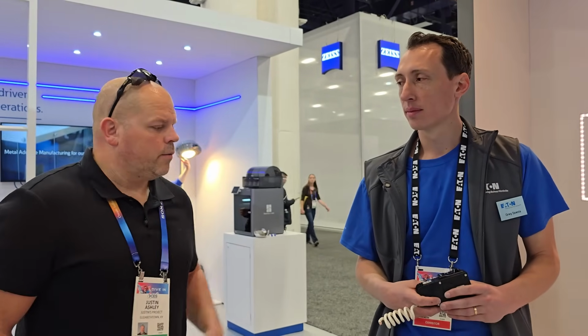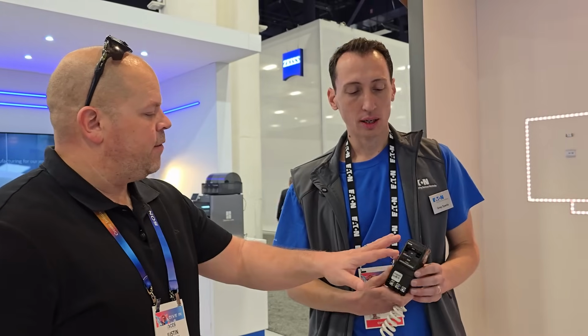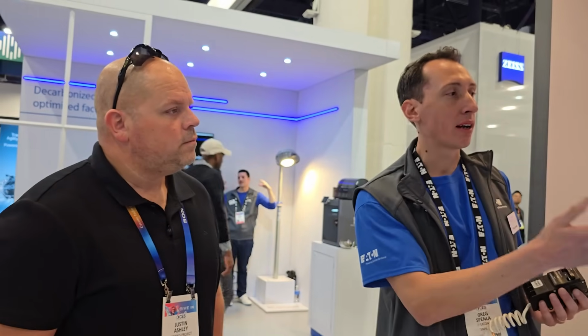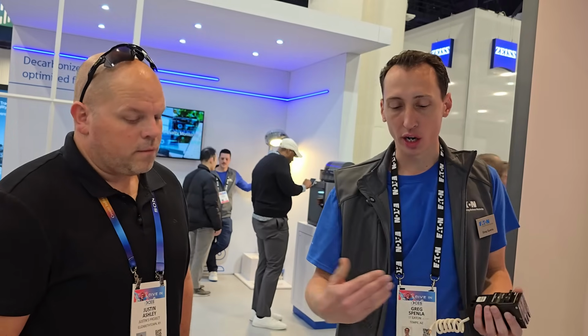All right. So you've got this in how many amps? What's the largest? This will be 15 to 60 amps. And again, this is a 2-pole breaker, so that's powering your 240 volt appliances, which is great because those are going to be the ones you want to shed. If you're paying 5 figures for a backup battery, are you going to turn the lights off? That's why you got it. We're going to drop things like your dryer and your hot water heater. We'll get you down to just those, lights, refrigerator. You're watching TV. If you don't want that load on, turn it off, or there are smart wall outlets that can empower that.